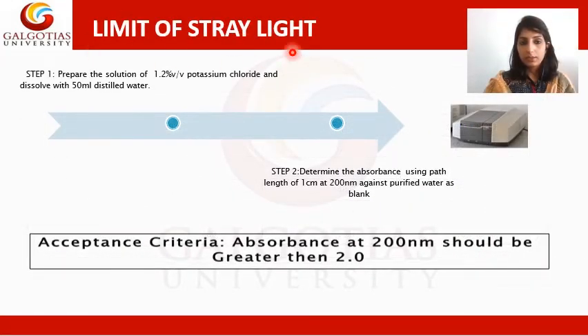Then comes the limit of stray light. We will check whether stray light is present in our instrument or not. Stray light is basically unwanted light which is present in your instrument. That light can be generated by various means, like internal reflections occurring inside the cell, or it may be due to extra light, outside light, coming into your instrument.